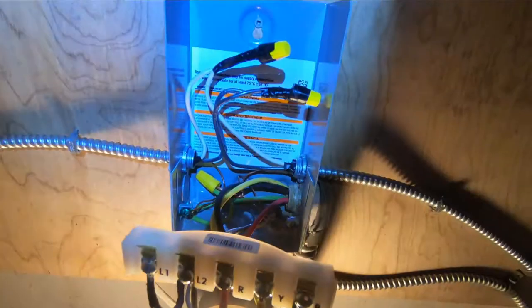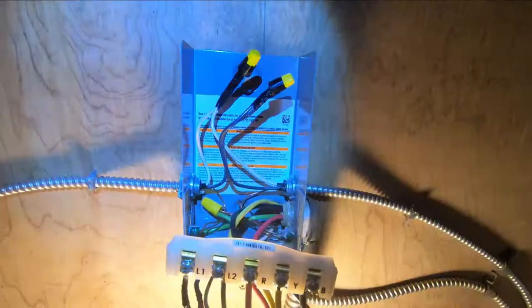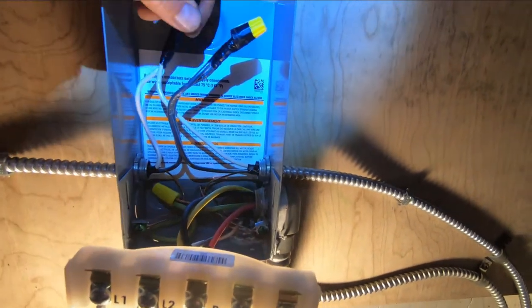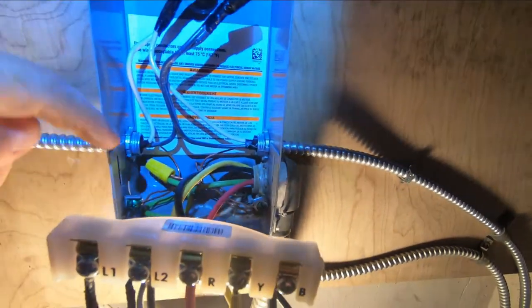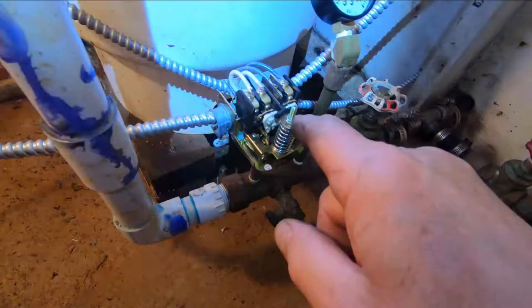Okay, so the power is off, we remove the cover. Inside the box you got power coming from the panel - 230 volts, 115 on each lead. Other than it grounding in here to the box, it's just passed straight on out through this cable down to your pressure switch.